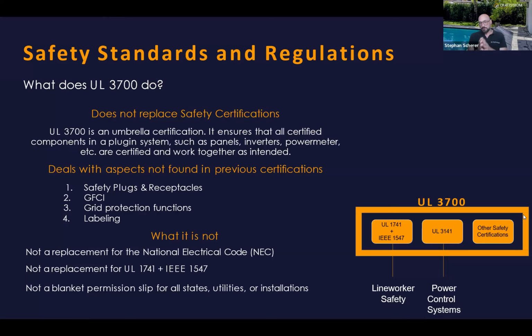At the moment, for instance, it still says it needs to shut off in 2 seconds. That's very long for our purpose. And because of our inverters having been certified to German standards, and discussions also with UL, at this point industry standard is that everything shuts off in less than a second, as quickly as 0.2 seconds. That's not just for line worker safety, it's also for consumer safety.